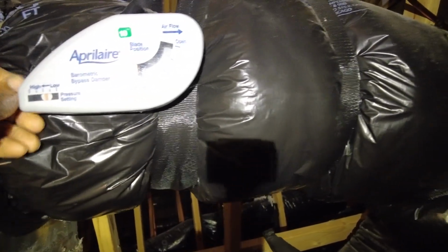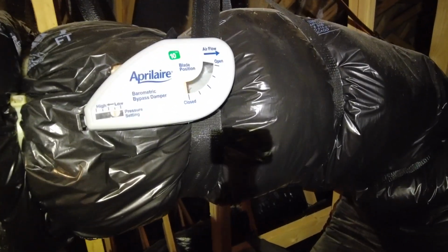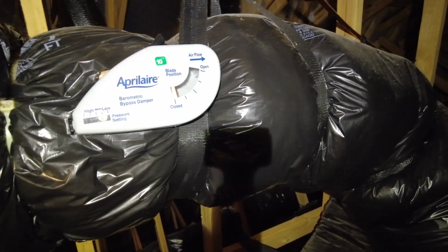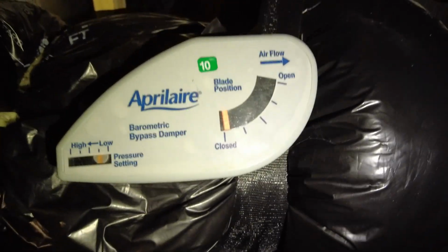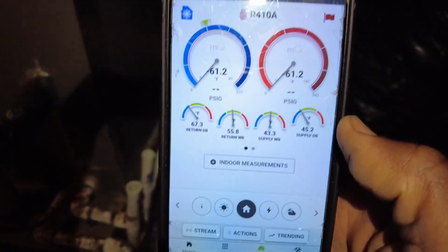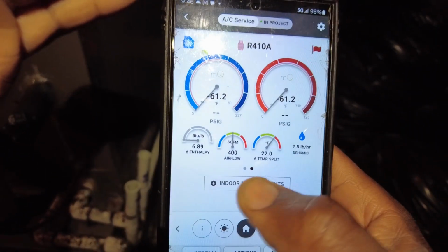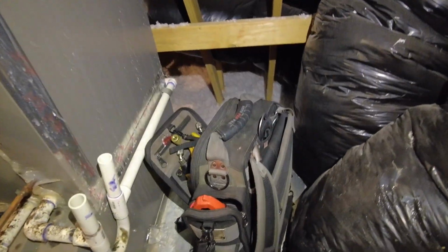Okay. So look, I'm going all the way back to where it was. See, it's just not closing back down. Yeah. We'll have to fix that. We'll have to figure that out. So as you can see, now you got a much more accurate interpretation of what that return temperature really is. Temp split 22 degrees. And I just went ahead and I'm going to lock it down for now. I'm just going to keep it closed down. I'm going to check my static pressure to see if we even need it, to be honest with you.